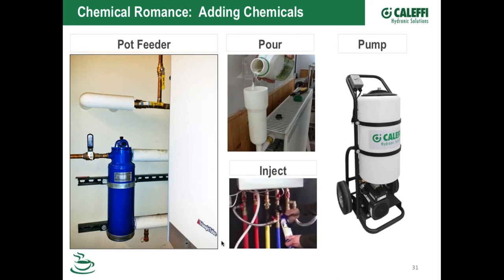On bigger systems, commercial buildings often have pot feeders where you take the lid off, dump your chemical in, then open a couple of ball valves so it flushes out of the pot feeder into the system. For example, if you've got a radiator at a high point in the system, you could use a little funnel like this - probably from the UK - to pour the inhibitor or chemicals in and inject it. We also sell the hydrofill cart, or hydro flush cart, which has a pump on it so you can pump fluid in. You could run a cleaner through the system with our pump cart for a couple of days to clean it out.